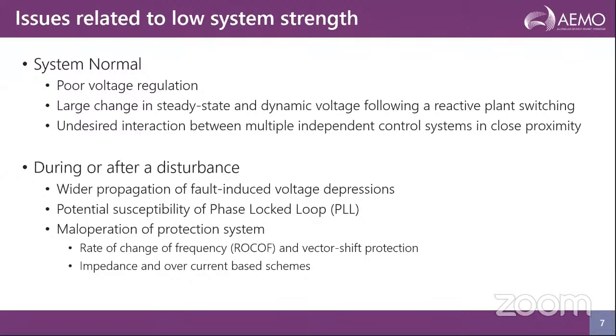During the fault, as the voltage angle movement is large and fast, it can often be difficult for the PLL to keep track of the angle change, and you might see instability arising from the plant, and the plant can trip off. The voltage angle transient could be misinterpreted by the protection system, particularly rate of change of frequency (RoCoF) and vector shift protection. They are prone to mal-operation in a low system strength environment.